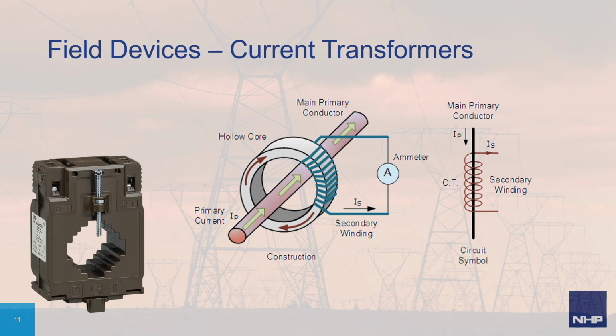The CT is arranged so that the current that is induced and flows in the secondary circuit, shown as IS in the image, is a faithful representation of the primary current, but reduced in magnitude by a precise ratio. Most CTs have a solid core like the one shown, but CTs with split cores are also available. These make it easy to clip the CT over a cable or a bus bar without disturbing any of the mechanical connections. There are also electronic CTs, which are not current transformers in the true sense, but rather current transducers. These commonly generate a 333 millivolt signal at full primary current, but require a dedicated instrument to interpret their signal.